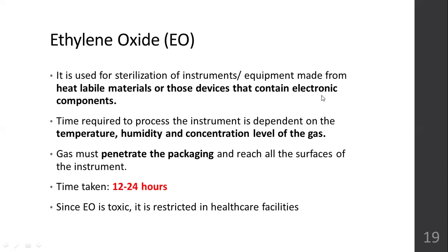It will take 12 to 24 hours for one cycle of ethylene oxide sterilization. And it's a very toxic gas. Ethylene oxide gas is very toxic. So usually in healthcare facilities, we don't recommend this. Okay. For industrial plants and all, ethylene oxide plants can be kept.